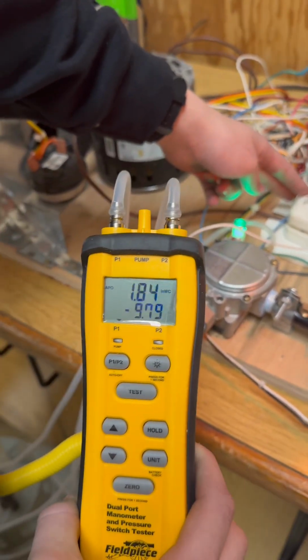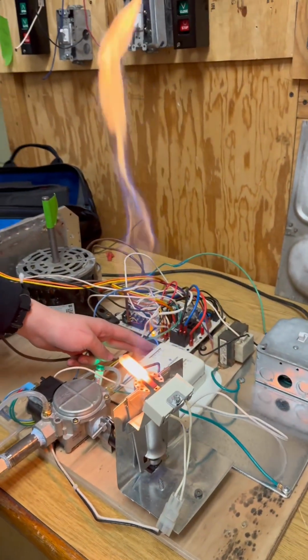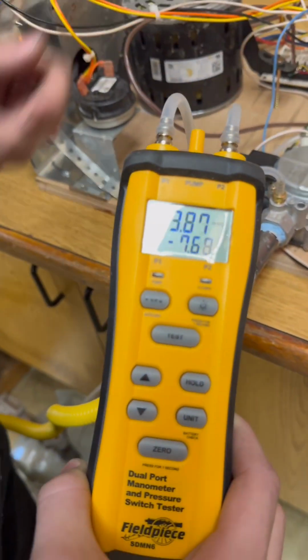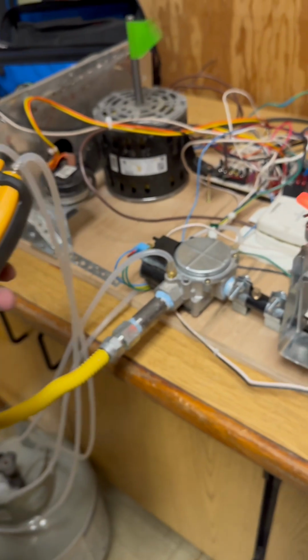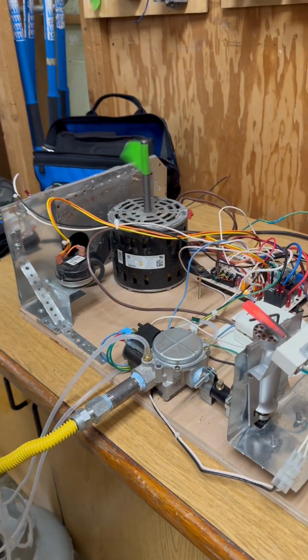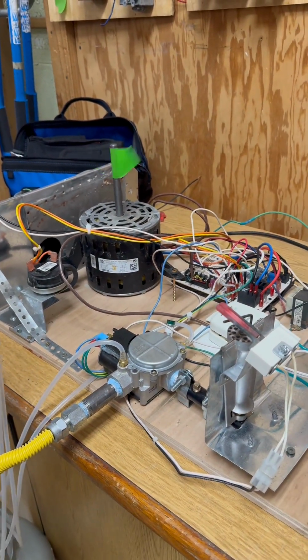Here's the light. We got our flame. 3 inches of water column. So that proves that our gas valve is now working, and we had a faulty crimp on our board.